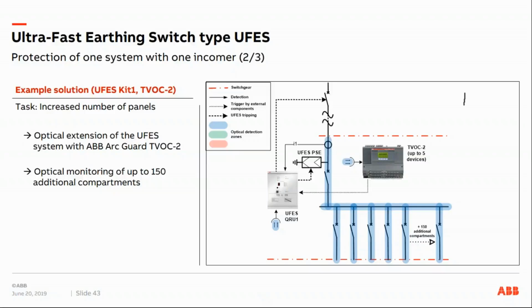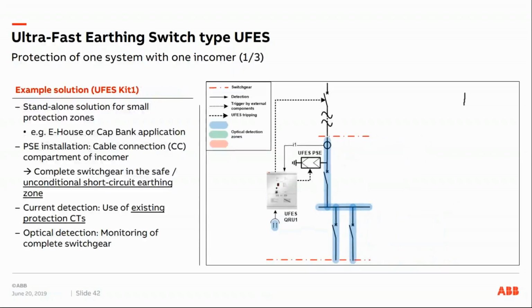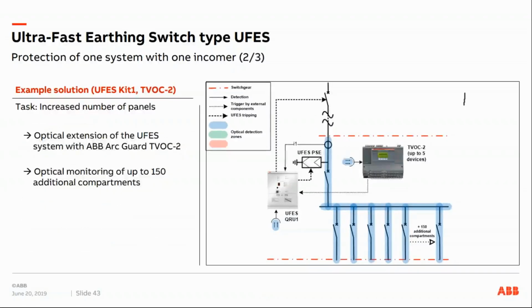Here we have another option with the first one, with the QRU1, and here in combination with the arc guard, if you need additional optical extensions to protect additional panels, as you can see here. And here we can have up to 150 additional compartments monitored by the TVOC and then protected by the primary switching element.